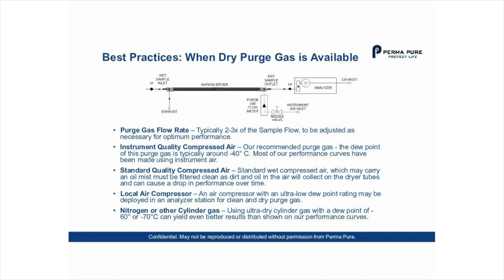We want to start with best practices concerning times when dry purge gas is available. All of our performance curves have been generated using minus 40 degrees C dew point instrument air. This is a typical specification for dried compressed air found in chemical process plants, refineries, and laboratories where compressed air is available. That is not always the case, but it is the most common way to test the performance of the dryer, which is why we use it in our literature.